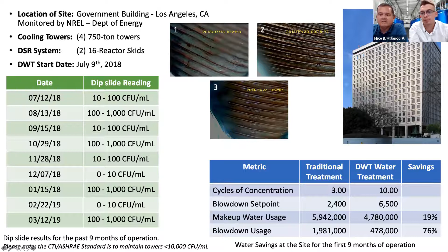What's also fantastic about this process is we went from 3 cycles of concentration to in excess of 10. The calculated measured savings was about 19% in makeup water and a 76% reduction in sewer discharge. Subsequent to this study, we've actually gotten up to 24% overall savings year over year.